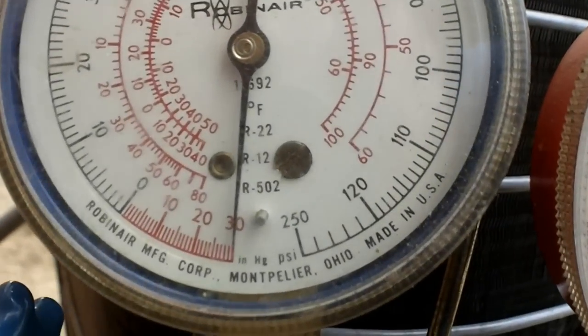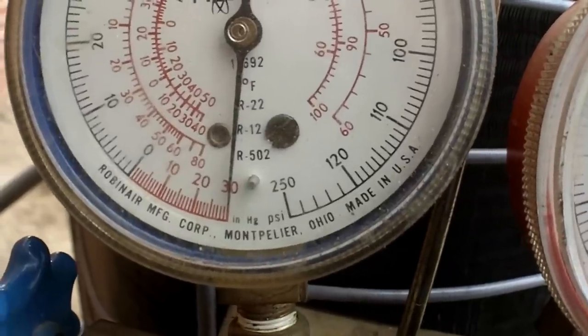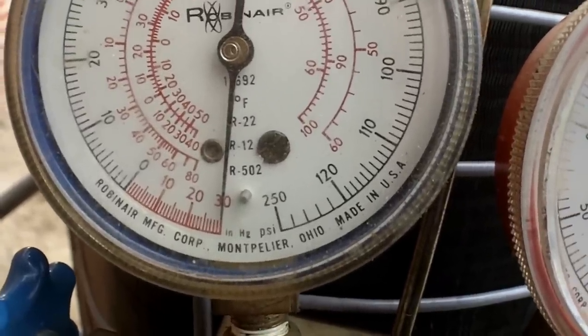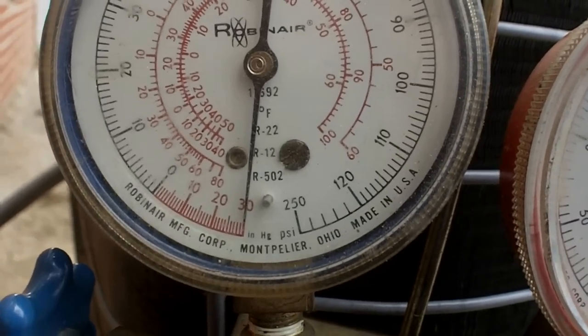All right, well, it's drawn it down just to about 30 inches of mercury, so it pulled it down within just a minute. So I'll let it run to evacuate the system and then charge it up.